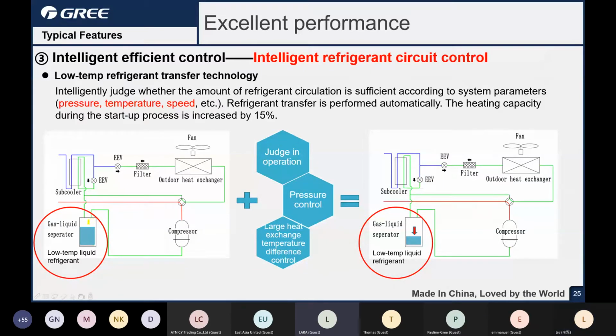And in heating, we can even supply some gas to the separator, making the liquid evaporate and circulate faster. So the heating capacity during the startup process is increased by about 15%, because we can distribute some hot gas to the liquid gas separator to make it evaporate and circulate faster, to get a quick start in the heating mode. Okay, that's the intelligent refrigerant circuit control.